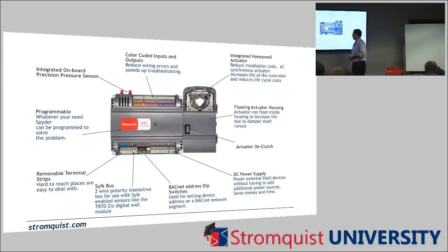These are pretty interesting little things right here. BACnet, address dip switches, and Sylk bus. So BACnet we're going to talk about in a little bit, and you'll notice that anytime you're doing anything with BACnet, you can always tell if it's a BACnet controller because it's going to have little dip switches on the controller. So that's how you can seem smarter than other folks: look at it and go, oh, that's BACnet. And they're looking all over the place and it doesn't say BACnet anywhere on there. Well, how the heck did you know that? Well, that Rob guy at Stromquist in that intro to DDC class I took 5 years ago told me if it had dip switches on it, it was BACnet. So Sylk bus is a proprietary comm bus that we're going to talk about in a little bit.